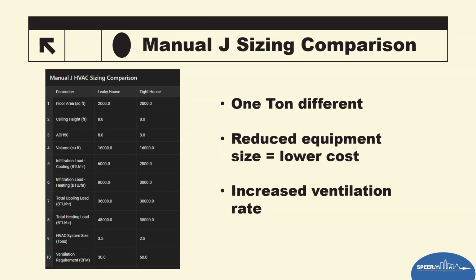On the flip side, though, if a leaky house was there, and we said this a second ago, if the Manual J and the energy modeling calculations were using a tight house, but now there's a bunch of leakage, that's off. That's a missed target. Same thing on the flip side. If the modelers are assuming it to be leaky and they build a tight house, now it's off as well. And then the capacity is wrong.